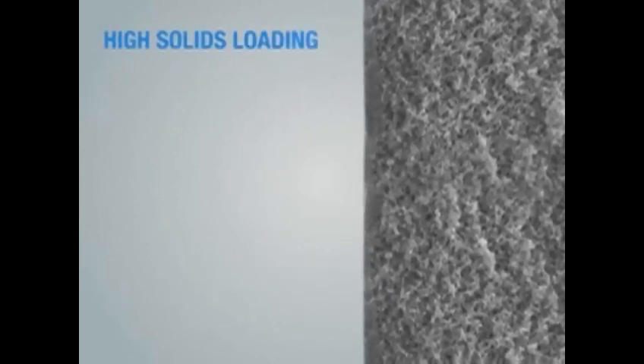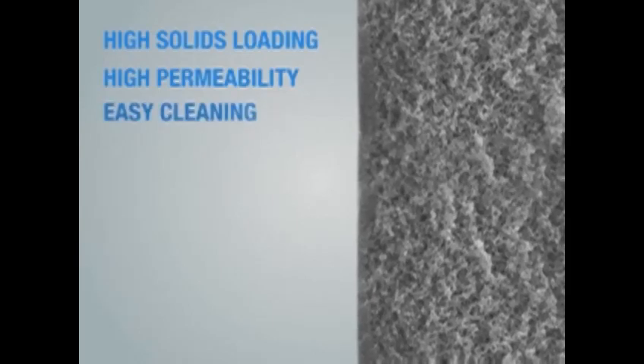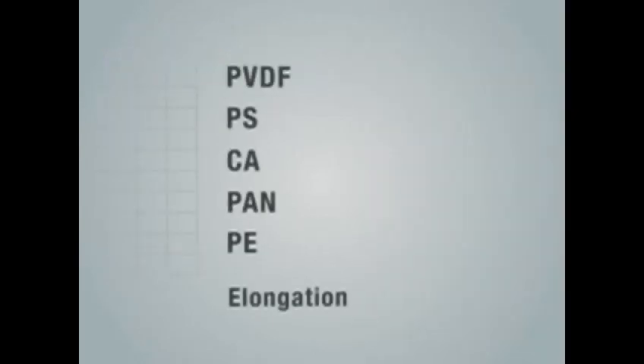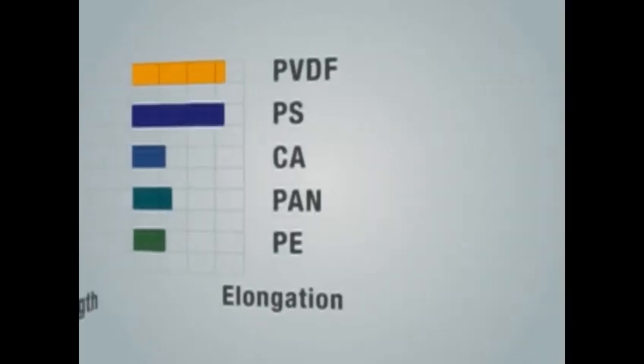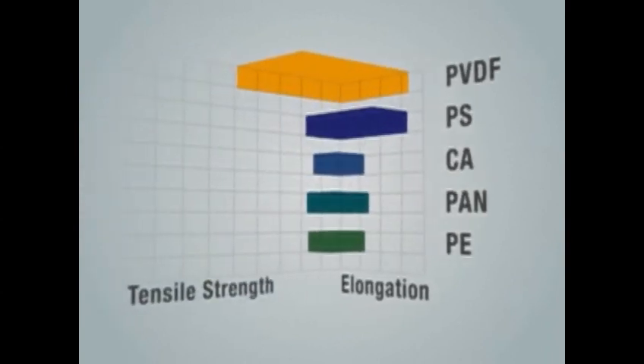The unique gradient pore sizes, smallest on the outside of the membrane and largest on the inside, provide benefits including high solids loading, high permeability, and easy cleaning. Such a feature leads to high porosity, important for ensuring high operating flux, and it makes the fibers mechanically more robust.